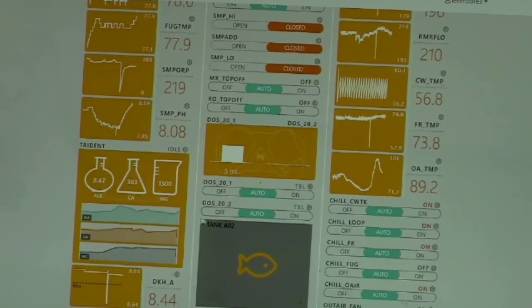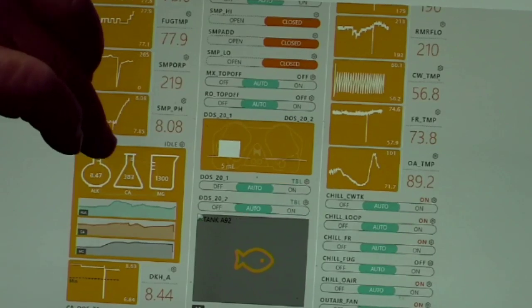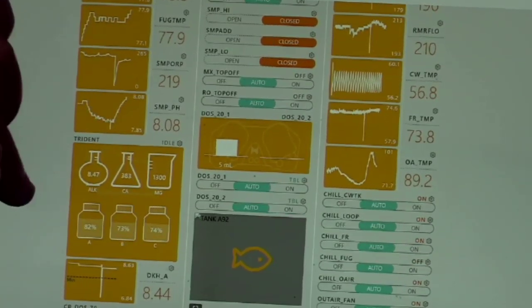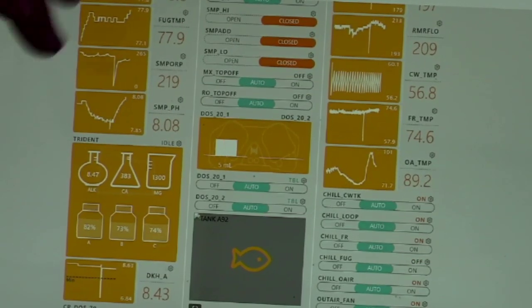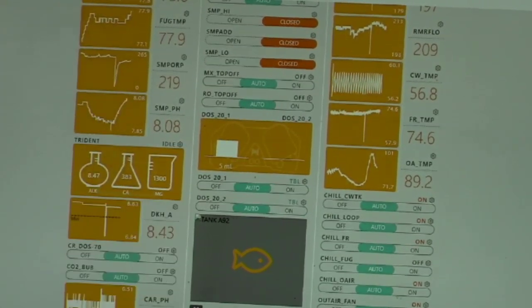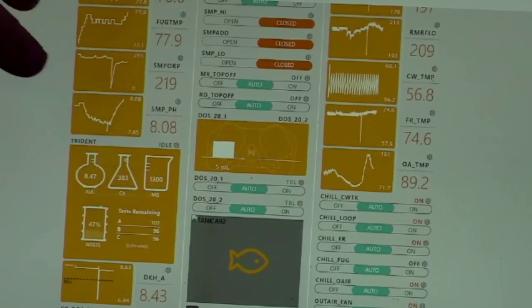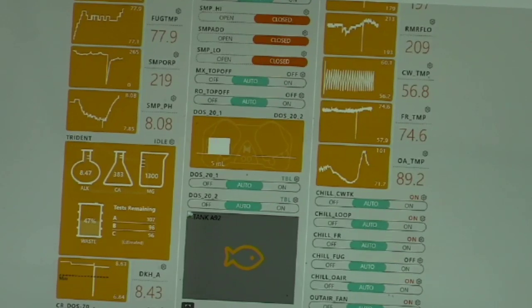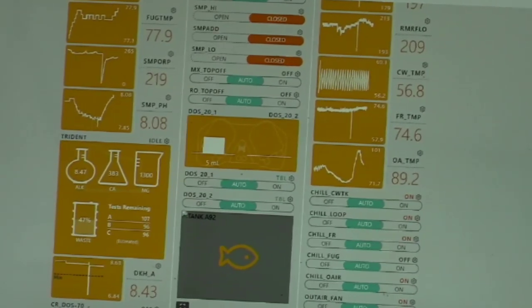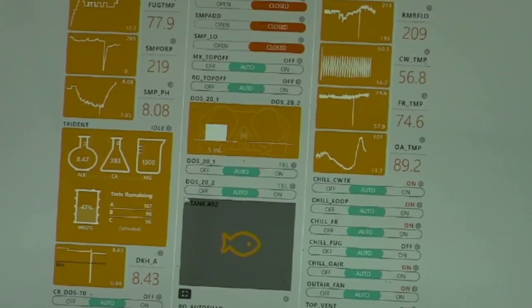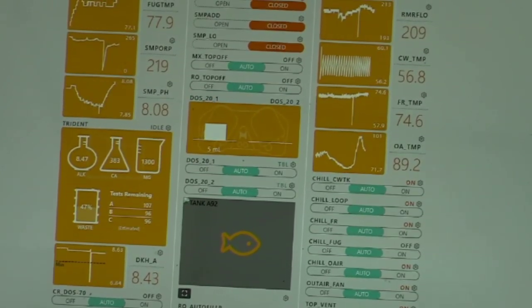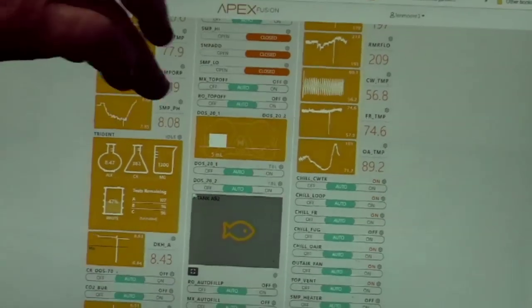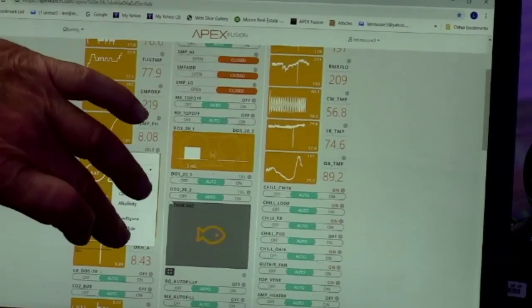And from the Trident, I touch on it, and it gives me little graphs on three categories: alkalinity, calcium, magnesium. Touch it again, it gives me the reagents remaining. It says 82% reagents remaining, etc. Touch it again. And it tells me how many tests I have left. I have roughly 100 tests left before I need to refill my reagents. And it tells me that my waste collection tank is 47%, so I'll have to change it in the next few weeks. And then it has the setups and the software programming.